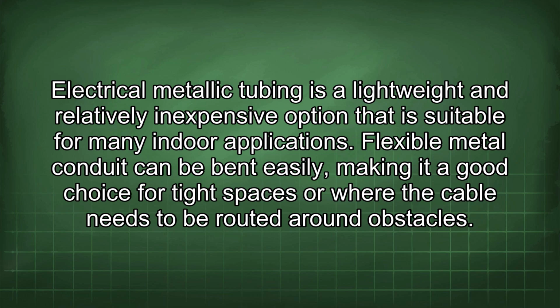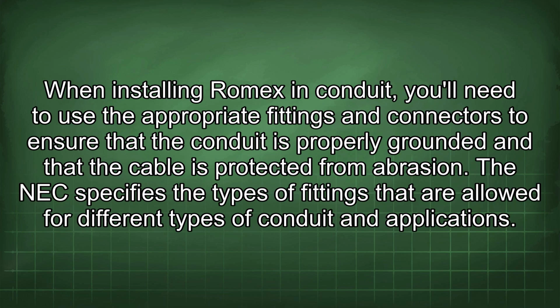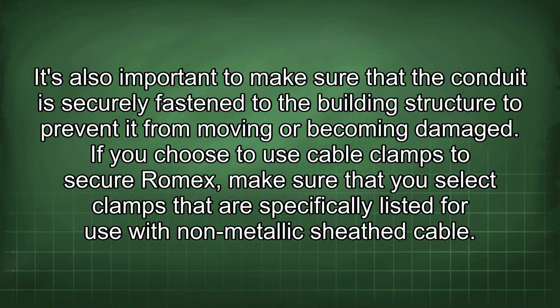Electrical metallic tubing is a lightweight and relatively inexpensive option that is suitable for many indoor applications. Flexible metal conduit can be bent easily, making it a good choice for tight spaces or where the cable needs to be routed around obstacles. When installing Romex in conduit, you'll need to use the appropriate fittings and connectors to ensure that the conduit is properly grounded and that the cable is protected from abrasion. The NEC specifies the types of fittings that are allowed for different types of conduit and applications. It's also important to make sure that the conduit is securely fastened to the building structure to prevent it from moving or becoming damaged.